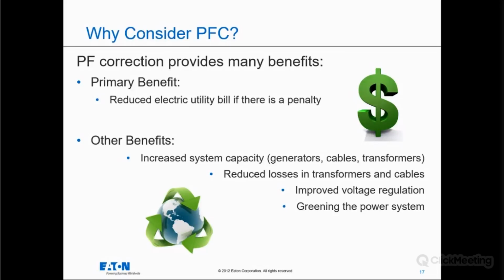You're also going to reduce losses in transformers and cables. Anytime you flow ampacity, there are also system losses there. So if we are providing that reactive current locally to the motor, we're again not pulling it through our MCC, through our switchgear or our transformer. So we're going to reduce the losses in those types of equipment.